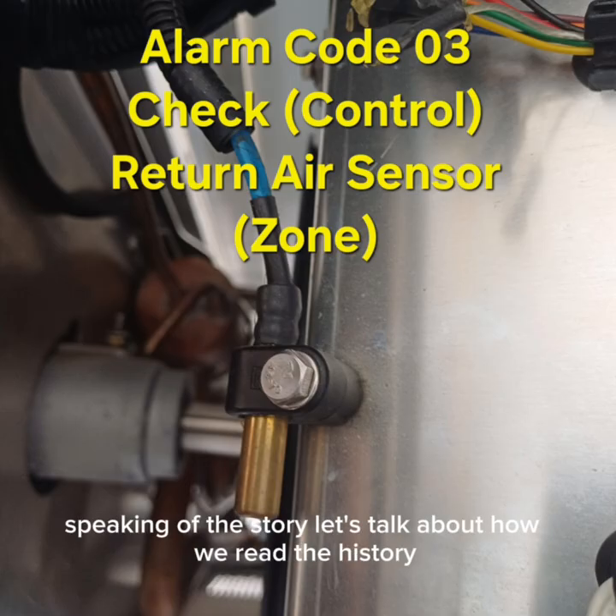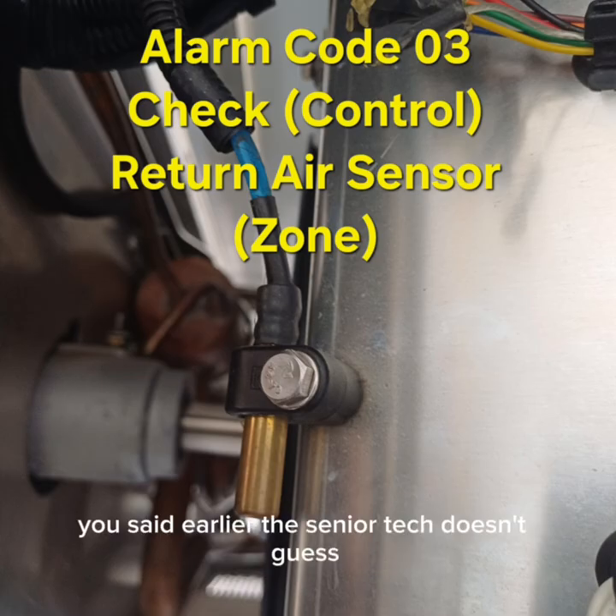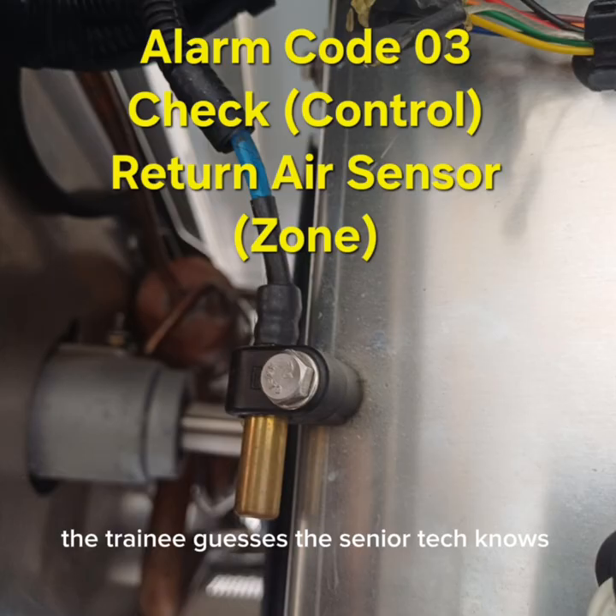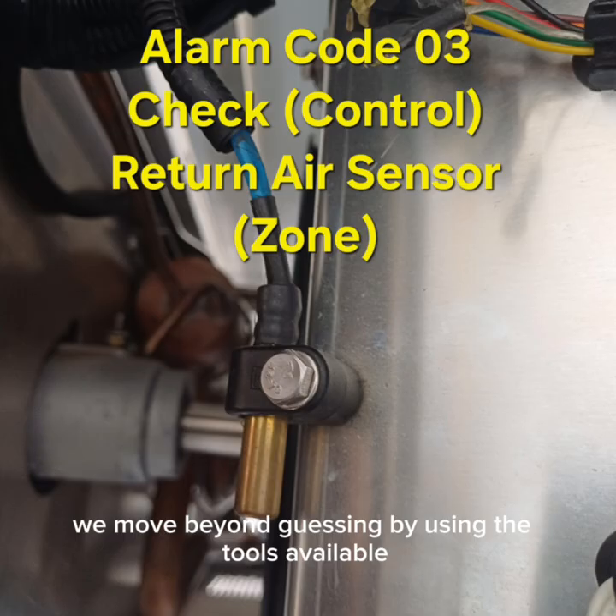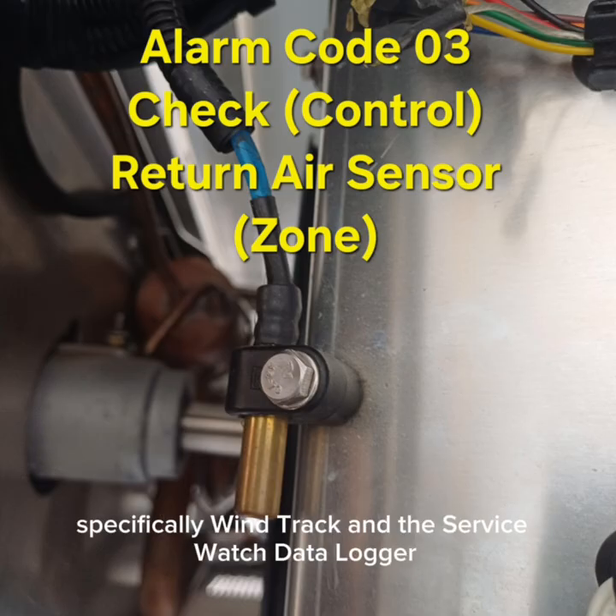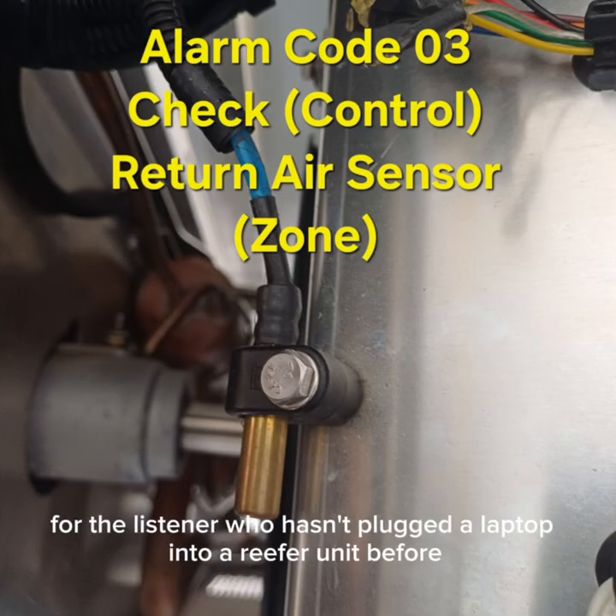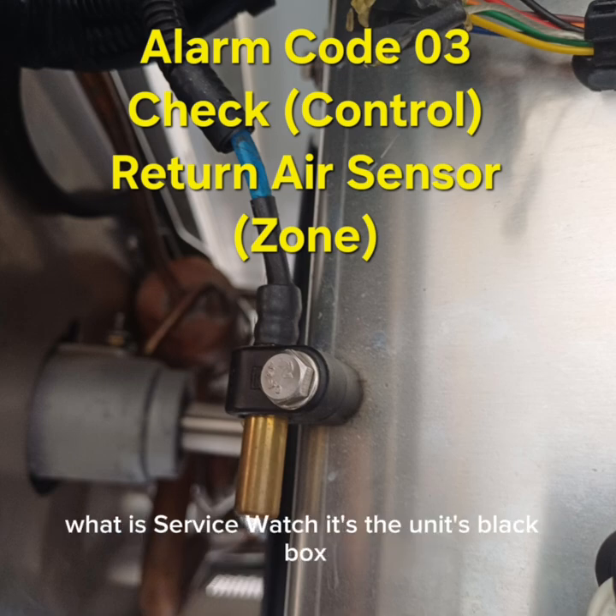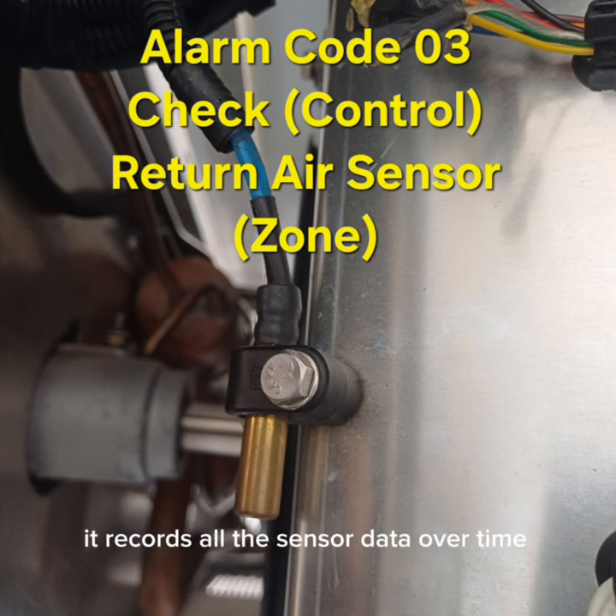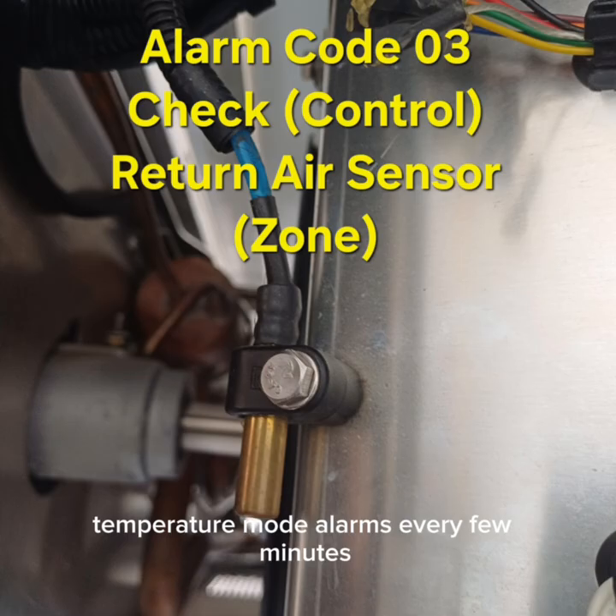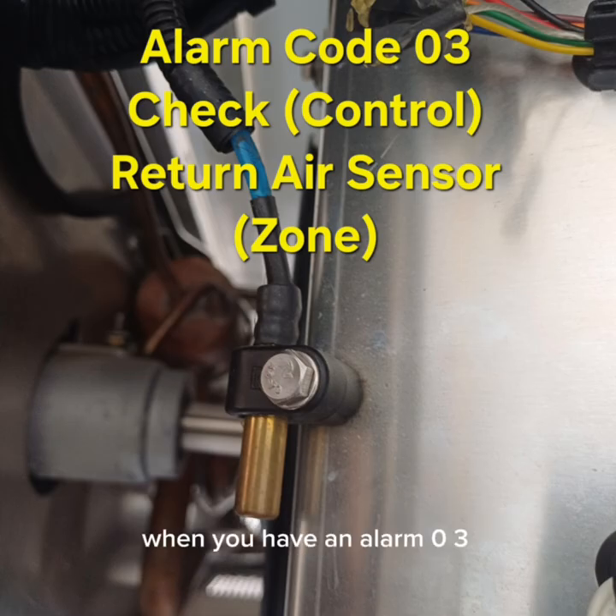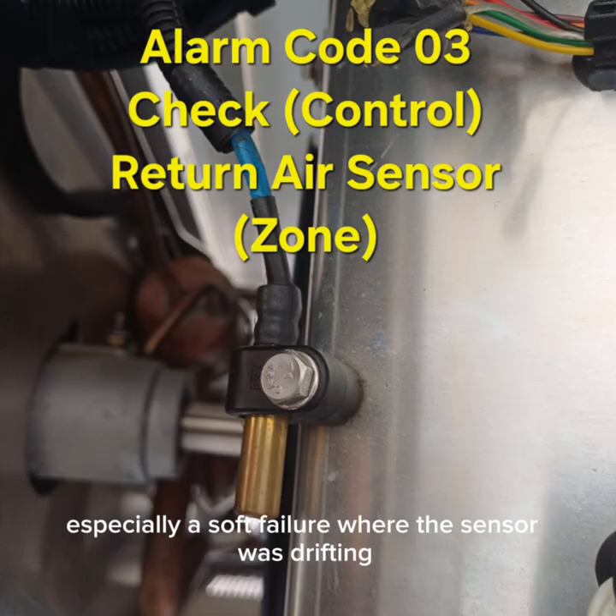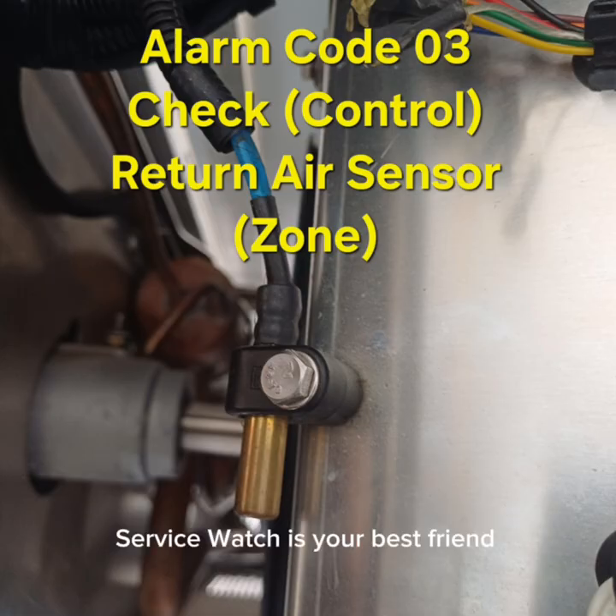Speaking of the story, let's talk about how we read the history. You said earlier the senior tech doesn't guess. The trainee guesses. The senior tech knows. Never guess. We use data. We move beyond guessing by using the tools available, specifically WinTrack and the Service Watch data logger. For the listener who hasn't plugged a laptop into a reefer unit before, what is Service Watch? It's the unit's black box. It records all the sensor data over time, temperature, mode, alarms, every few minutes. When you have an alarm 03, especially a soft failure where the sensor was drifting, Service Watch is your best friend.